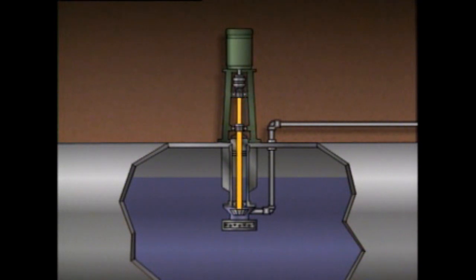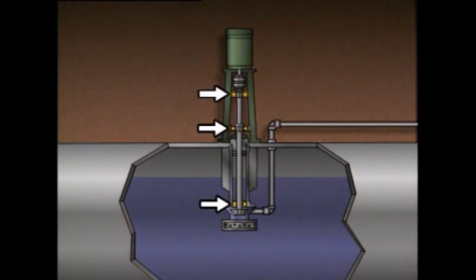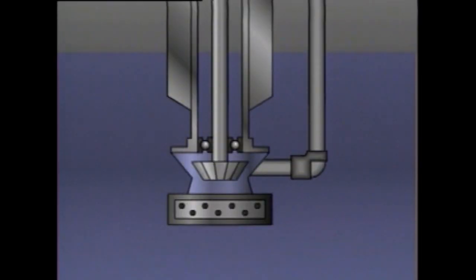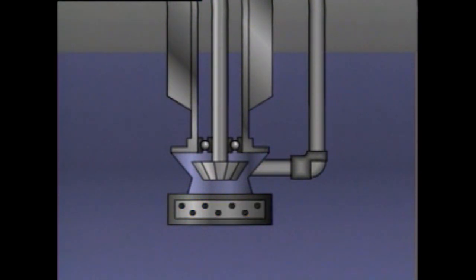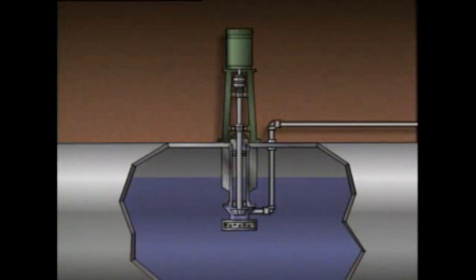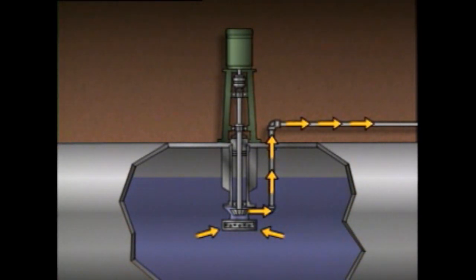The motor shaft is connected to the pump shaft by a coupling. This pump shaft is much longer than those found on most other centrifugal pumps, so several bearings are used to keep the shaft properly aligned. There is no suction piping on this pump; instead, the suction is submerged in the liquid being pumped and is covered by a strainer, which prevents trash or debris from clogging the pump and causing excessive wear. The pump's impeller is also submerged, ensuring the pump is always primed — meaning the casing is filled with process liquid. During operation, liquid is drawn in through the suction and pumped through discharge piping that extends up and out of the tank.